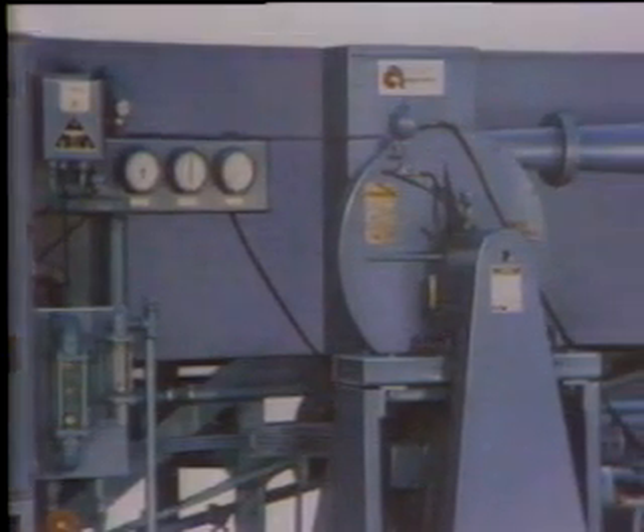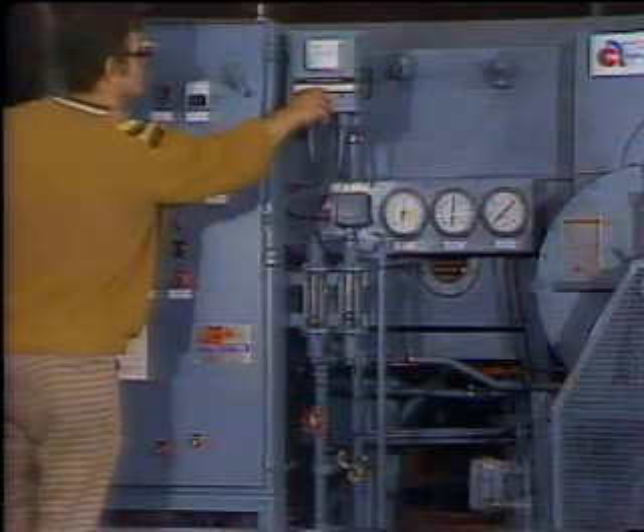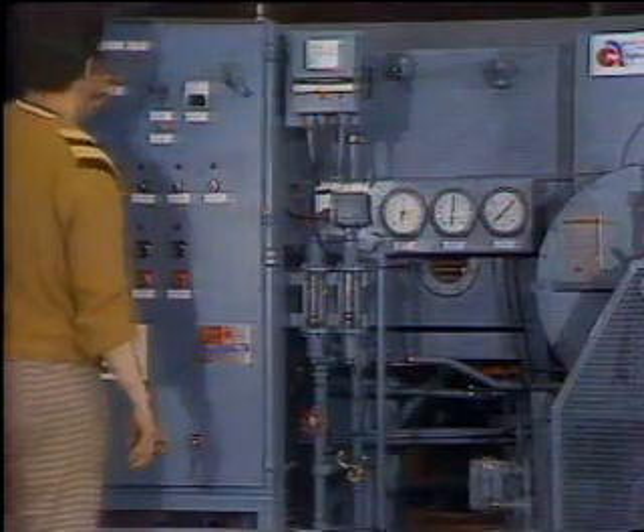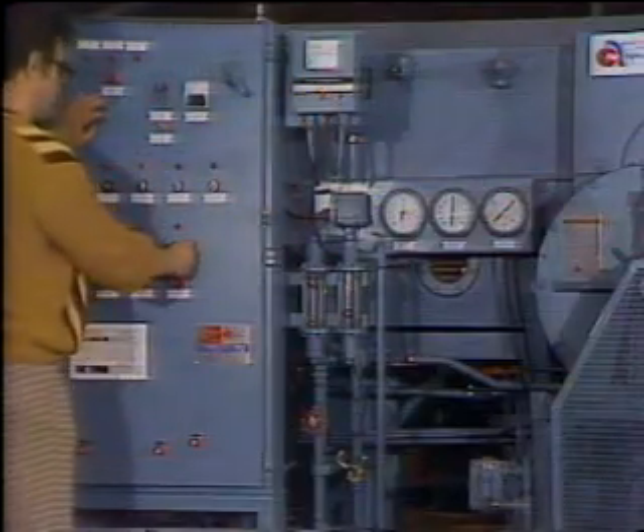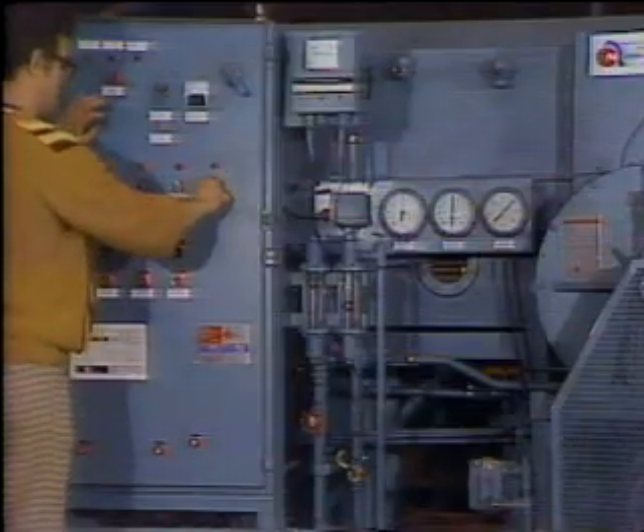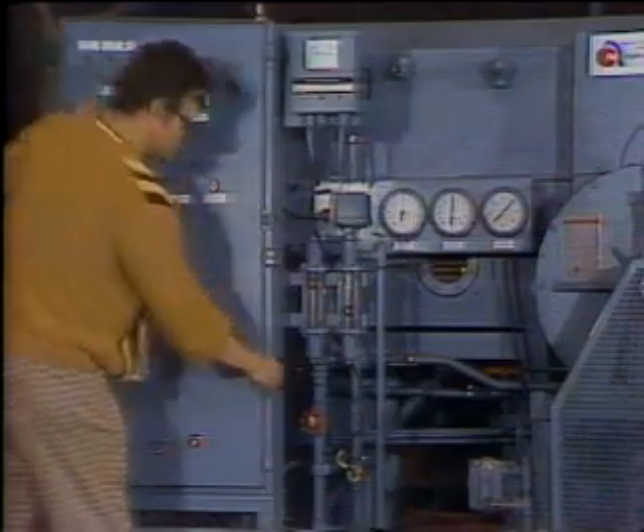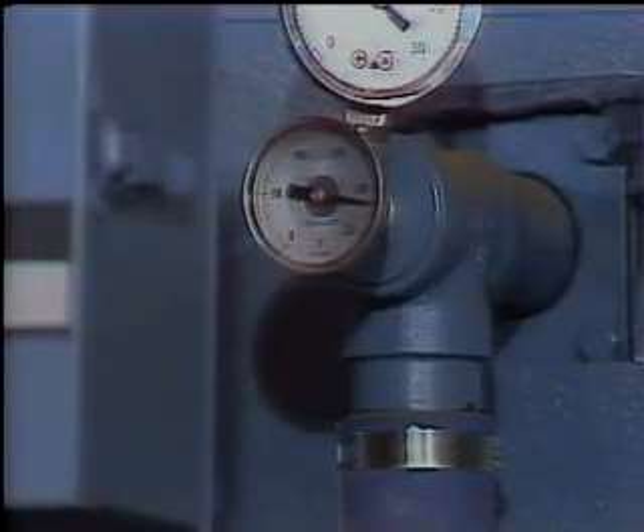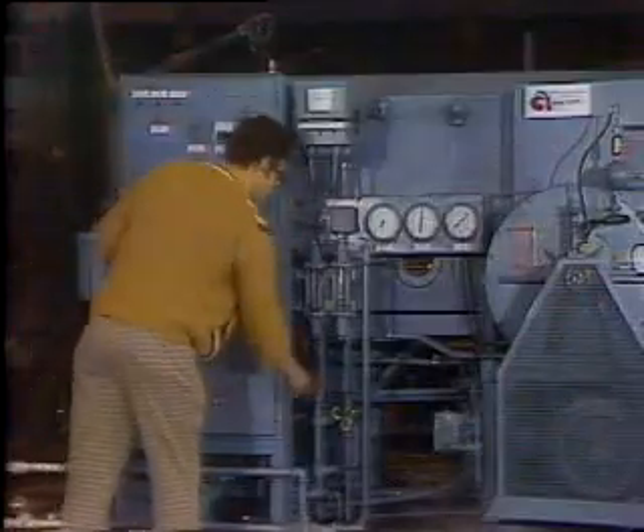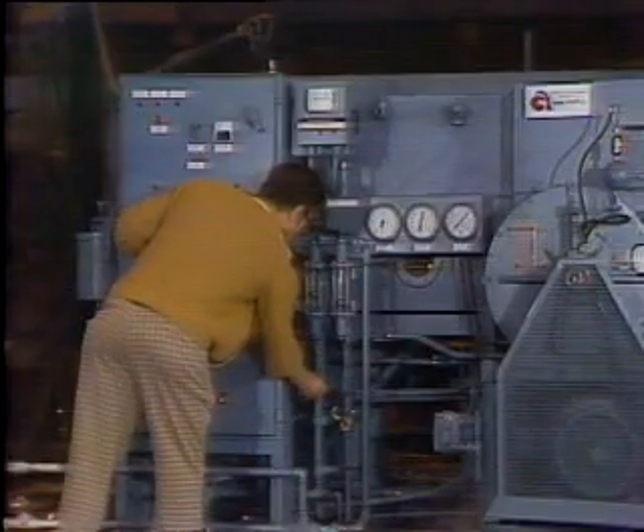centrifugal compressor. To get it started again, turn the salinity meter off and push the reset button on the front panel. Then, start the lube oil pump, turn the heaters on, and shut the feed water off. Check the boiler water level to ensure that there's plenty, because a low water level will also trip the master control circuit. When the recirc temperature reaches 214 degrees, go through the startup procedure again.